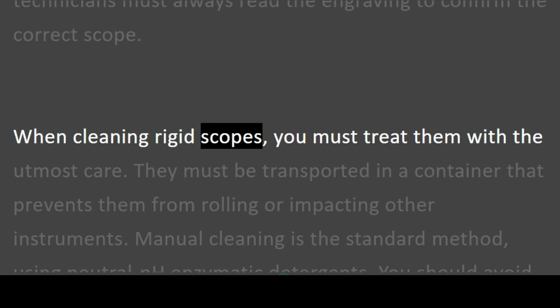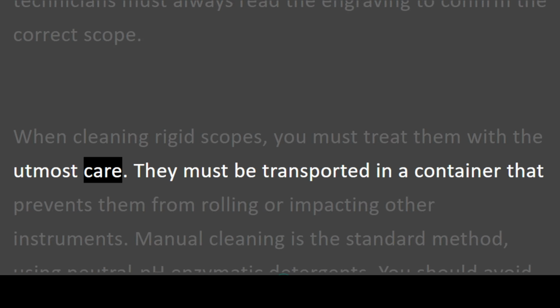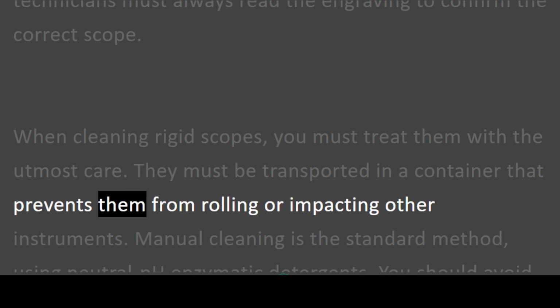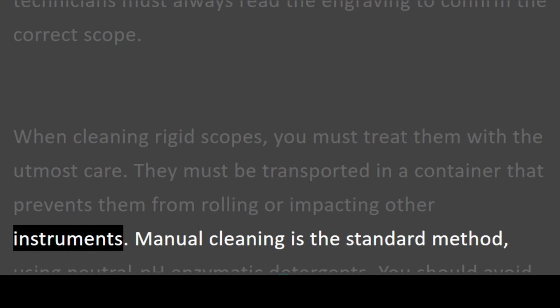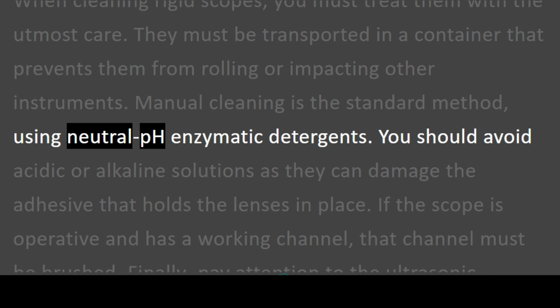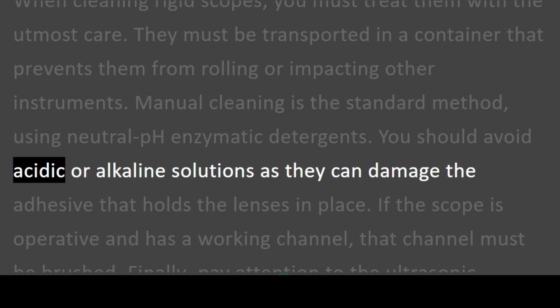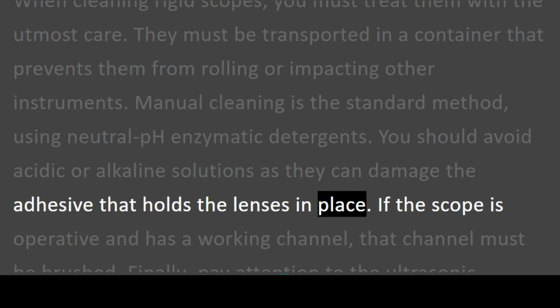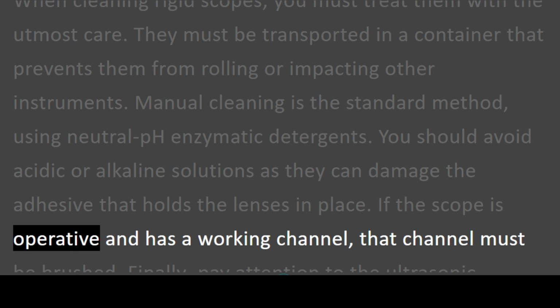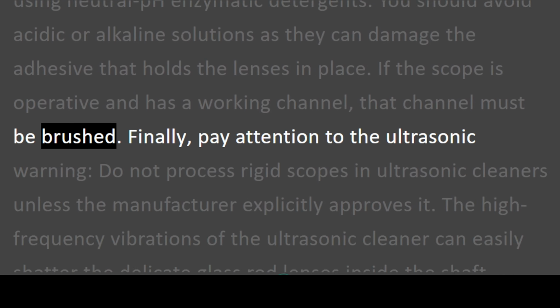When cleaning rigid scopes, you must treat them with the utmost care. They must be transported in a container that prevents them from rolling or impacting other instruments. Manual cleaning is the standard method, using neutral pH enzymatic detergents. You should avoid acidic or alkaline solutions as they can damage the adhesive that holds the lenses in place. If the scope is operative and has a working channel, that channel must be brushed.